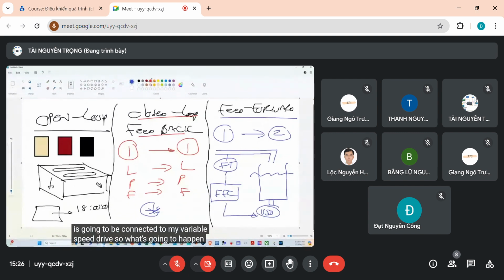What's going to happen is I'll measure a disturbance to my tank. If the flow increases, I can run the variable speed drive faster to compensate. If the flow decreases, I can run it slower to compensate. I am measuring one thing to control something else - in this case, measuring the flow to control the level.